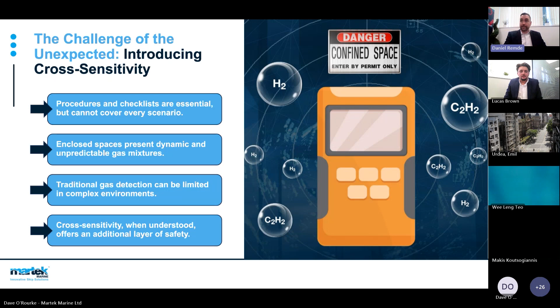So what is cross-sensitivity? It's when a sensor responds to a gas other than what it's targeted for. For example, a carbon monoxide sensor will typically also respond to acetylene, hydrogen, and other solvents and gases, because of the similar chemical properties that cause these gases to react within the sensor's element.